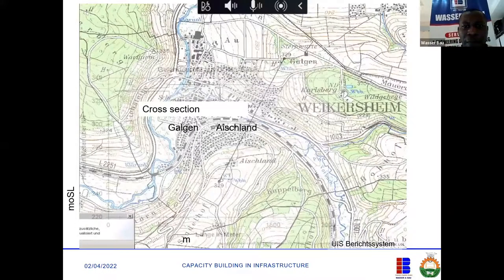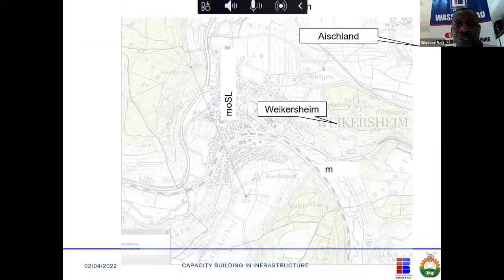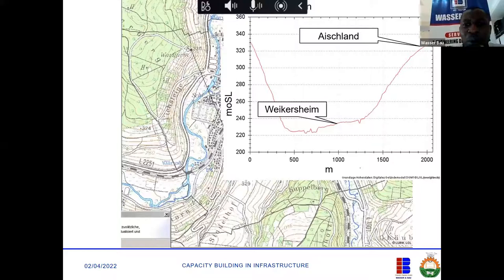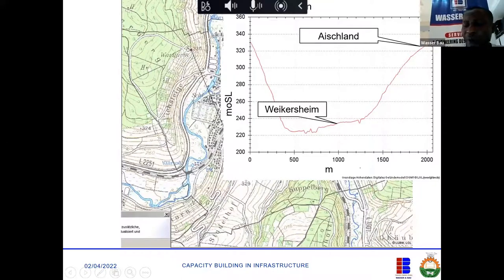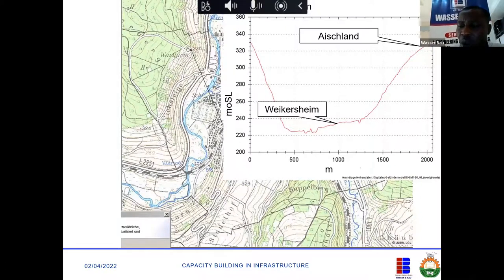You take a section of the area so that you look at where there will be potential problems. The reason for this is that most times when you want to design a centralized water supply system, you find out that a centralized system is not possible. So you go for decentralized - which simply means you have different boreholes and different elevated tanks within the same layout, because you can't pipe from A to B. So B will have a separate system and A will have a separate system.